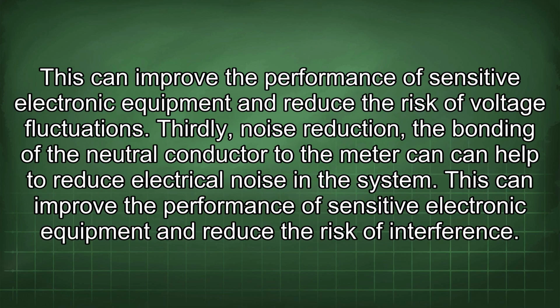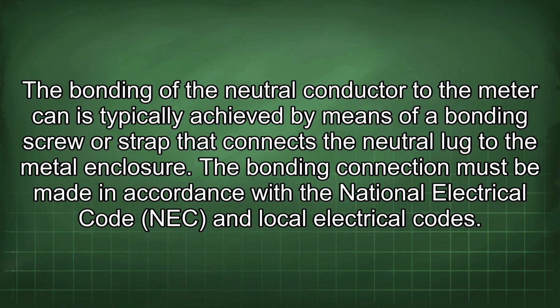This can improve the performance of sensitive electronic equipment and reduce the risk of voltage fluctuations. Thirdly, noise reduction. The bonding of the neutral conductor to the meter can help to reduce electrical noise in the system. This can improve the performance of sensitive electronic equipment and reduce the risk of interference. The bonding of the neutral conductor to the meter is typically achieved by means of a bonding screw or strap that connects the neutral lug to the metal enclosure.